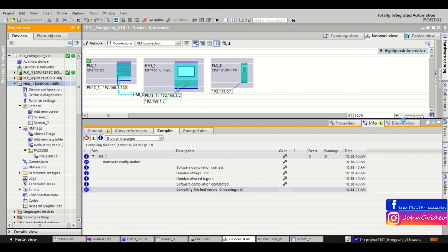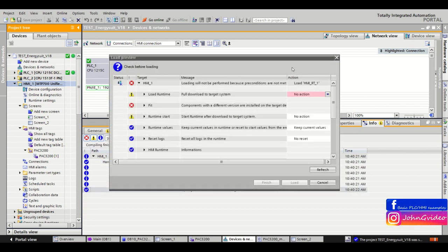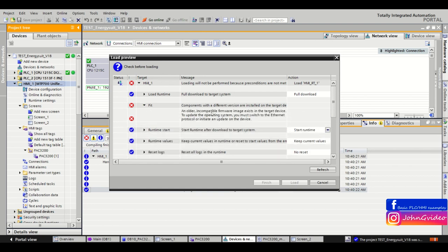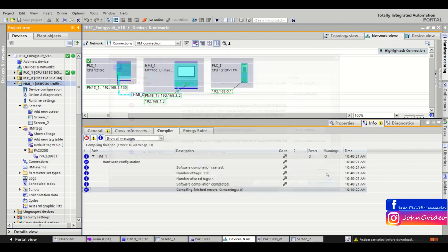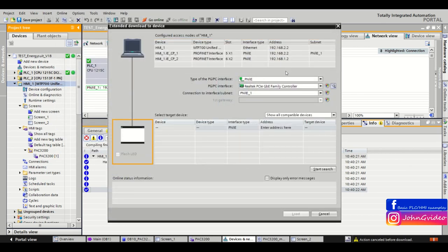I can see that my firmware in the panel is older than the firmware in my application. So I can't proceed with loading my application to the panel by the Profinet.